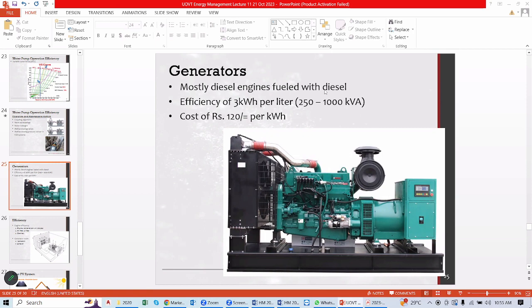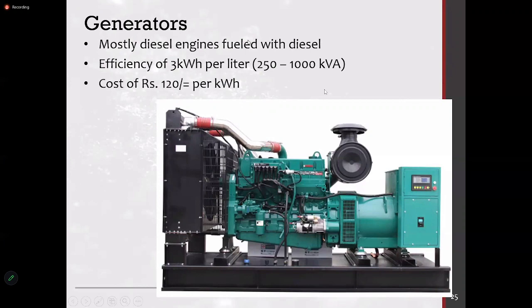So we are moving on to a little bit on the generators. These are mostly used during backup time, so not much of a usage, but there could be situations during power failures and stuff like that where you have to use the generator. So mostly diesel generators, roughly if you take efficiency, generally 1 liter should produce 3 kilowatt hours. So that is an important parameter that you can check.